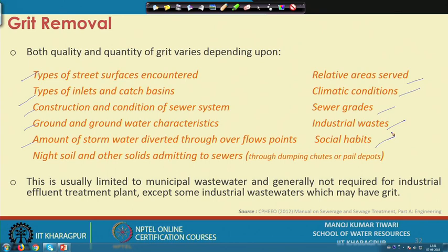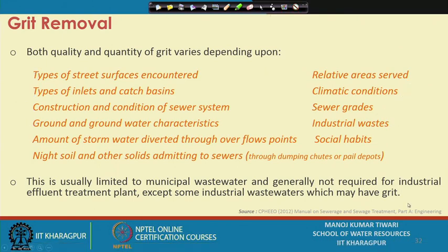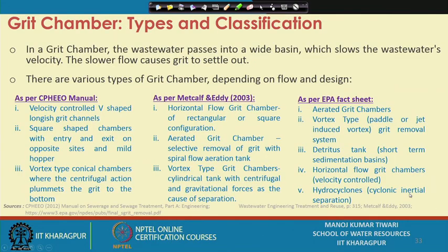Grit removal is usually limited to municipal wastewater and is generally not required for industrial effluent treatment plants, except for some industrial wastewaters that may have grit. Industrial processes are fairly organized and the kinds of materials expected in those systems are fairly standard. If the processes come from controlled systems with no possibility of grit materials entering the flow, one may actually avoid grit removal. However, in municipal sewage it is almost a certain unit that needs to be provided, as municipal sewage typically comes from open channels or sewer lines and contains a lot of grit material.